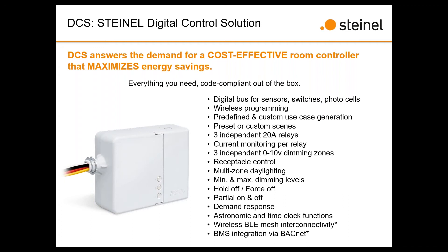We use a two-wire, non-polarized digital bus, which allows for very easy installation. You have two wires, you just stab into the two terminal blocks, and then stab into the two terminal blocks on the next device — that's it. No CAT5 cables, no RJ45 terminations, no pre-cut wire links, and no field terminations with six or eight small wire connections. That is the number one cause of pain in most CAT5-type install solutions — faulty terminations that commissioning agents spend a lot of time identifying and re-terminating. We've eliminated that entire concern.